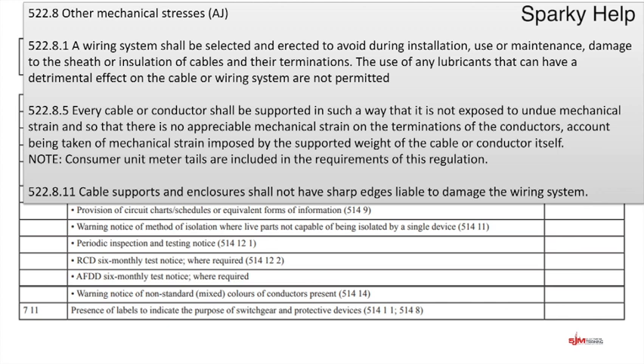And as I think I've said before, within the on-site guide they show a drawing of a meter and a distribution board and some tails, and they say this is what a clipped cable looks like, and they've drawn some clips on the cables. What some manufacturers have done is they've put in clamps effectively above the main switch which can support and clamp the cable within the distribution board. Not all have done it, but some have, and I think that's quite a good idea. Helps support it. So that includes your tails. Have they been clipped, cleated, whatever you've done, supported in some way?